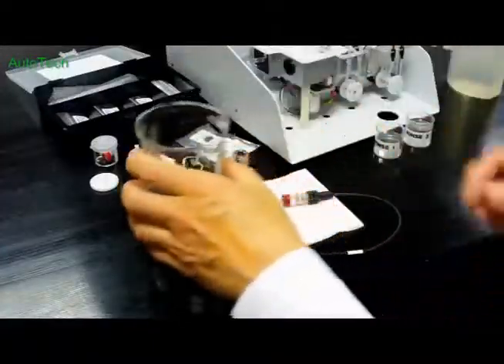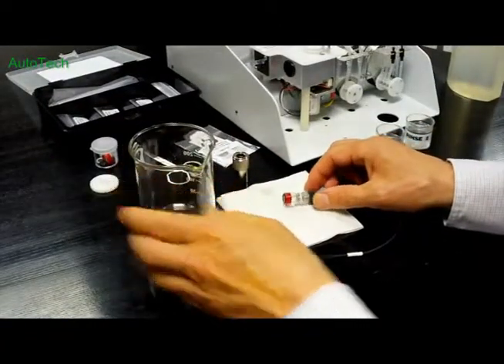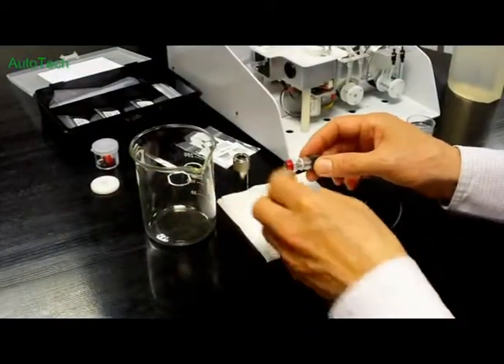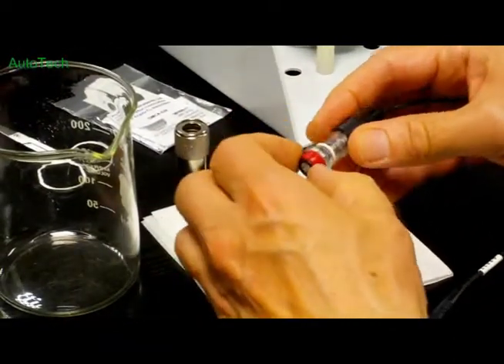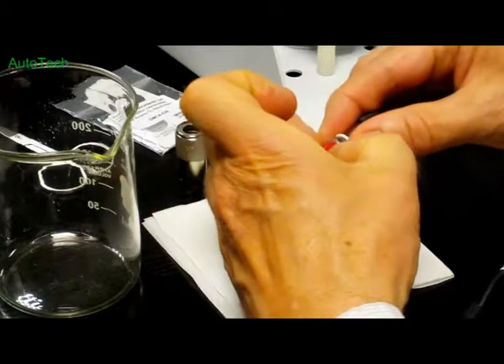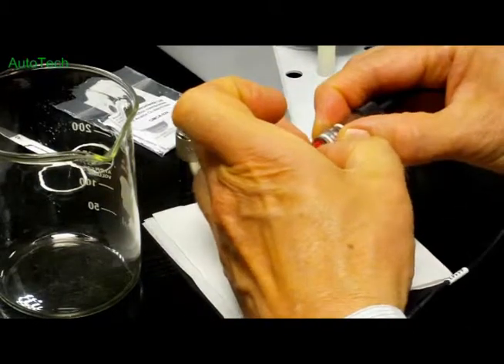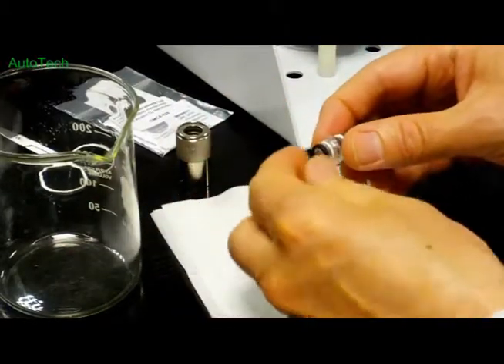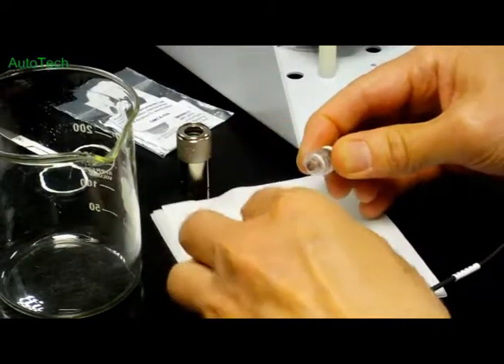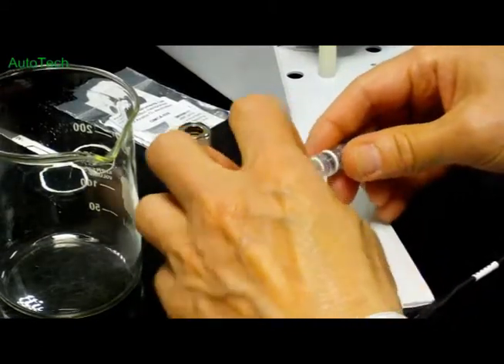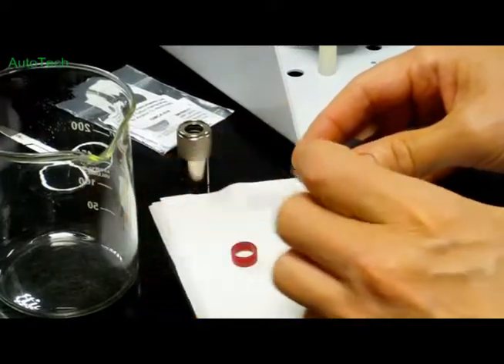So we'll need a suitable vessel to empty the contents of the electrode into, and start by removing the O-ring out of the O-ring groove, and removing the end crown, and then you can also take off the membrane O-ring, and at the same time remove the old membrane from the electrode.